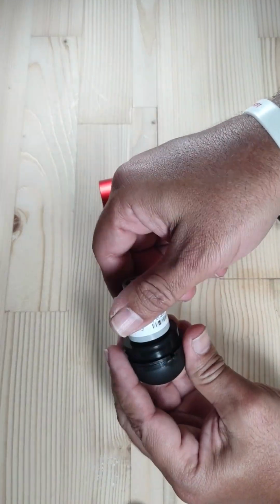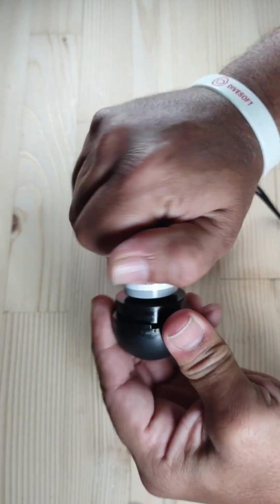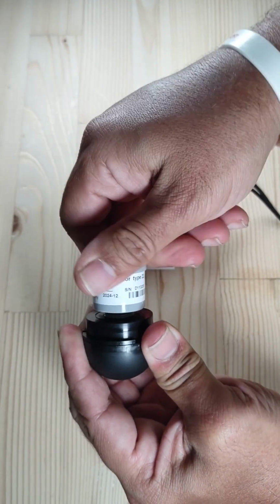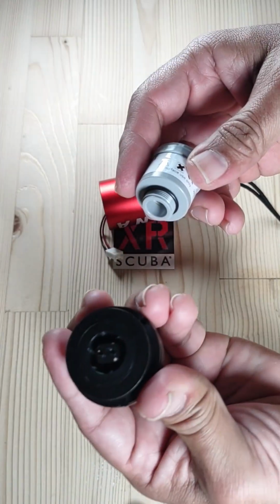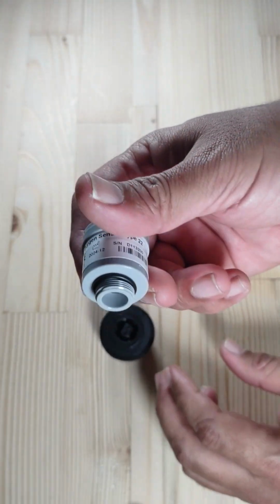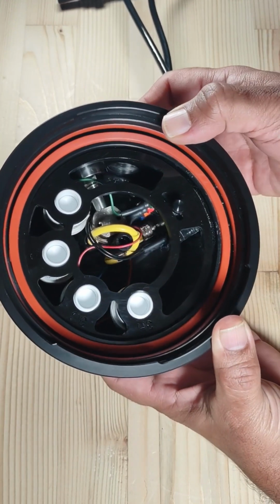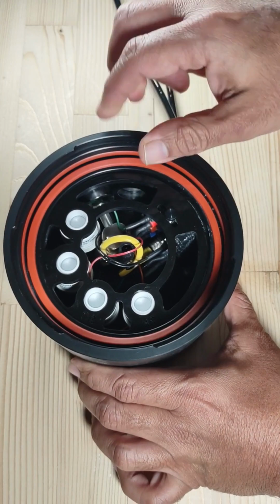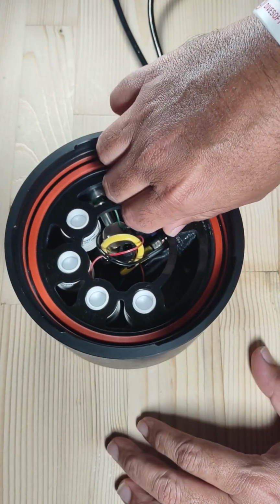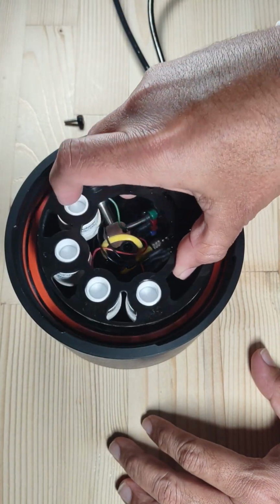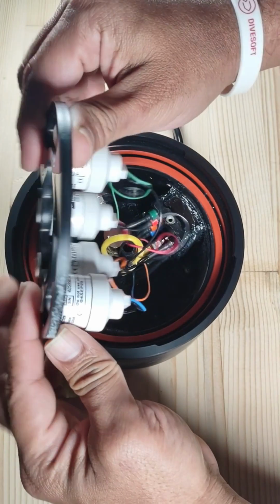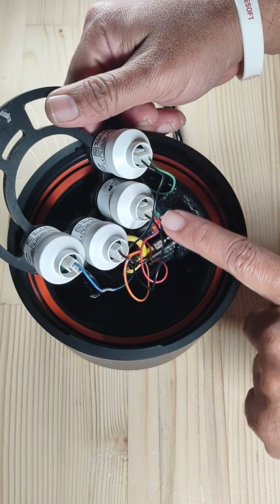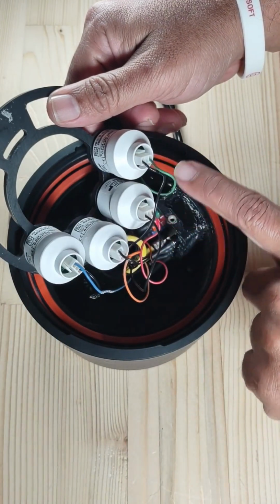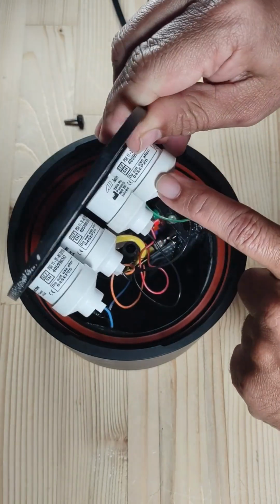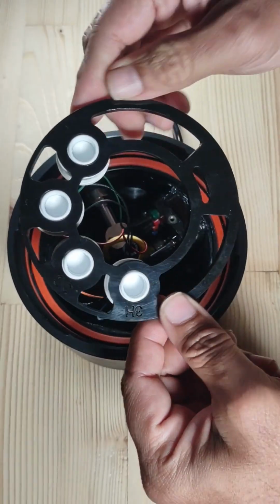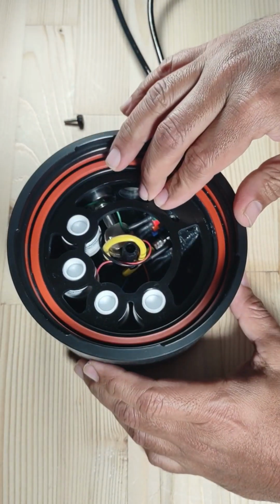Okay? Next, you unscrew the old oxygen sensor from the head. Okay, that's your old oxygen sensor. Now if you have a friend who dives a rebreather which uses the R22 Molex oxygen sensor, and your friend is about to change his sensor because rebreather sensors are changed more regularly than analyzer sensors, you could just ask him for a sensor because he's just going to throw it away. And that sensor should be perfectly fine to use in your analyzer. Of course, you will do a full calibration to make sure the sensor is working properly.